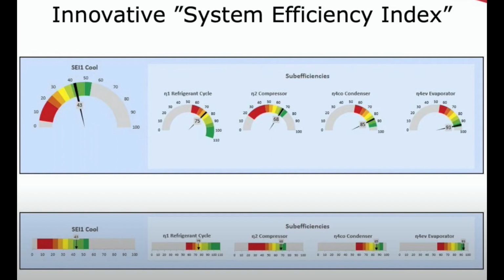Most times we visit a site, a chiller won't be working in the perfect conditions. Ambient temperature might be well out of range. The chilled water temperature also. The amount of load that we've got on the chiller is maybe not very high, but we're still expected to do a service on the thing.